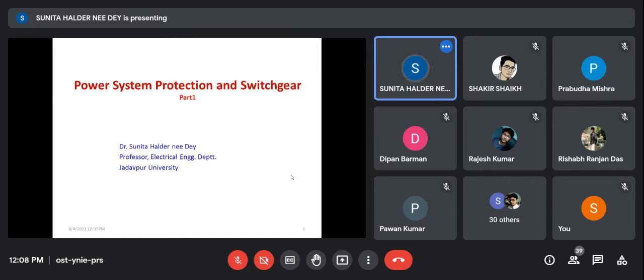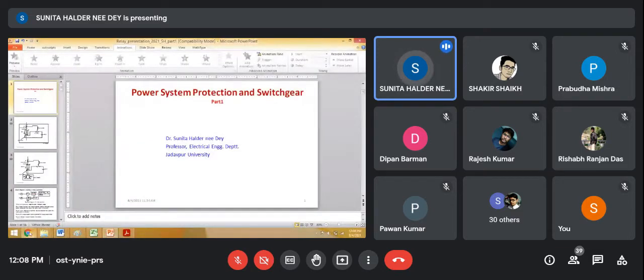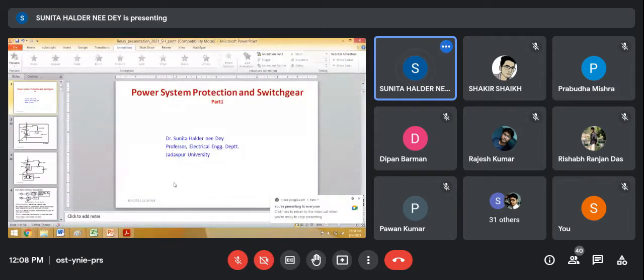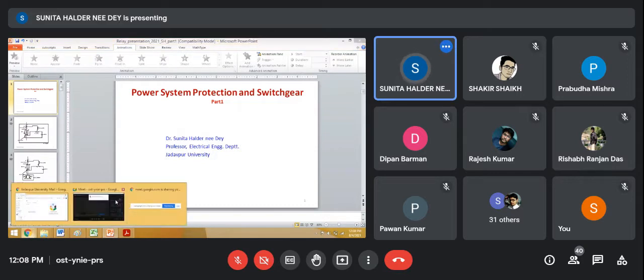Mainly the relay. Now relay is a very vast topic. It cannot be covered totally in a class. It is not possible, and it is updating every day. So whatever we will be taught in the class is the basic of relaying. In a practical system, it will be changed, varied from one system to another depending on system criteria. So there is no specifics. There are some guidelines, but there is no specific rule for relaying. So we shall learn those guidelines and the rules we can follow for relaying for protection purpose of a power system.